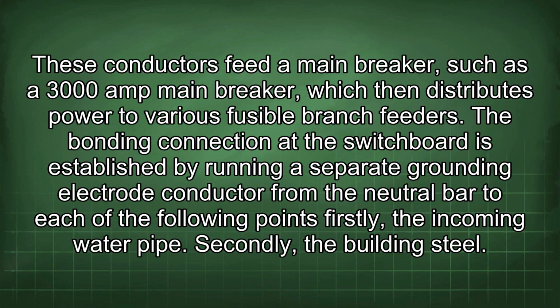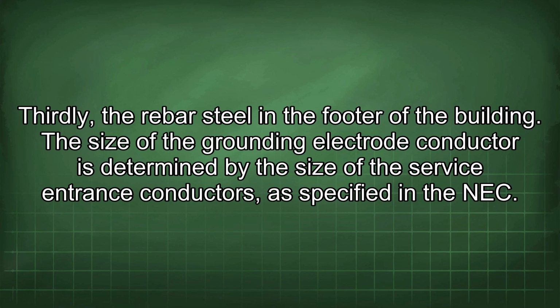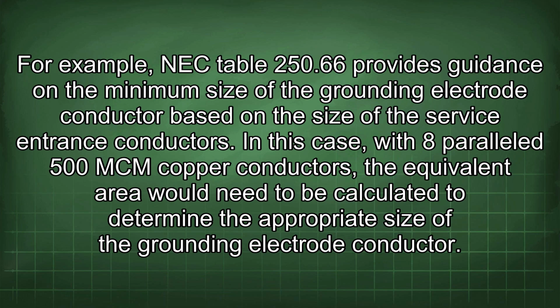These conductors feed a main breaker, such as a 3000 amp main breaker, which then distributes power to various fusible branch feeders. The bonding connection at the switchboard is established by running a separate grounding electrode conductor from the neutral bar to each of the following points. Firstly, the incoming water pipe. Secondly, the building steel. Thirdly, the rebar steel in the footer of the building. The size of the grounding electrode conductor is determined by the size of the service entrance conductors, as specified in the NEC. For example, NEC Table 250.66 provides guidance on the minimum size of the grounding electrode conductor based on the size of the service entrance conductors.